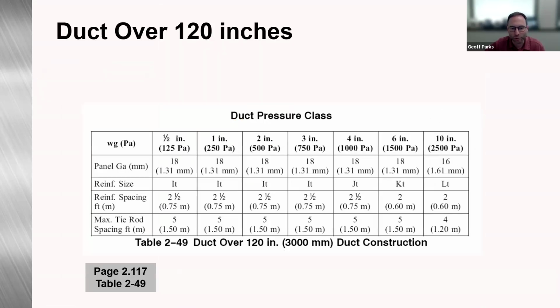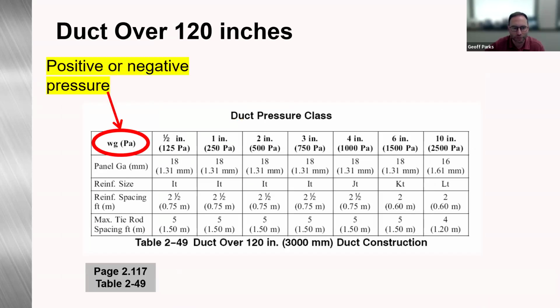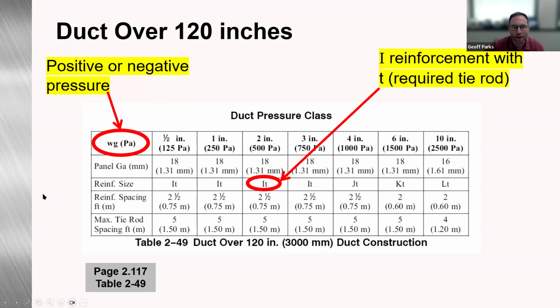So looking at table 2-49, first, our top row is our inches of water gauge, our pressure, and that's either positive or negative. Then our reinforcement size. Looking at this one here, an IT: I is our reinforcement, and T indicates that tie rods are required, like I mentioned before. And then we have our reinforcement spacings and our maximum tie rod spacing.